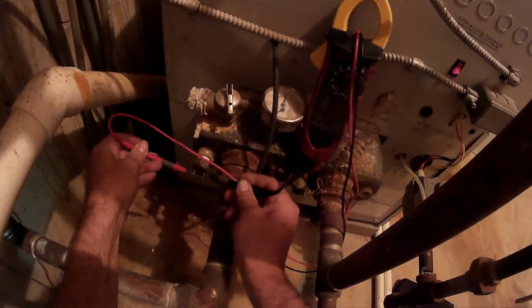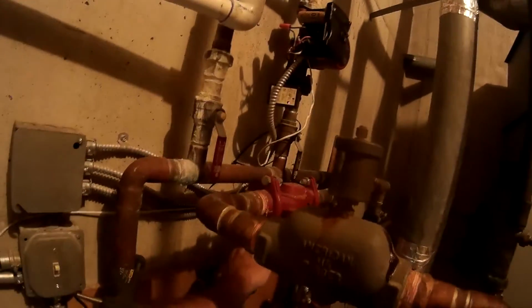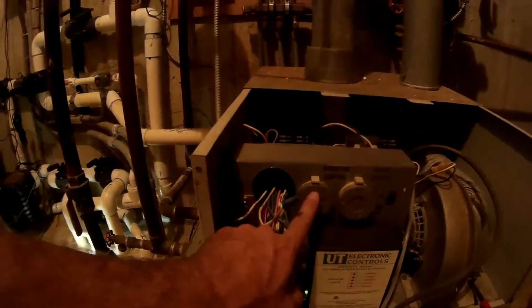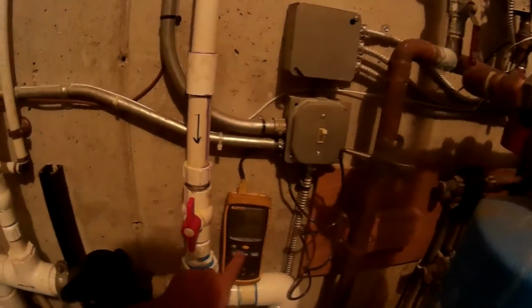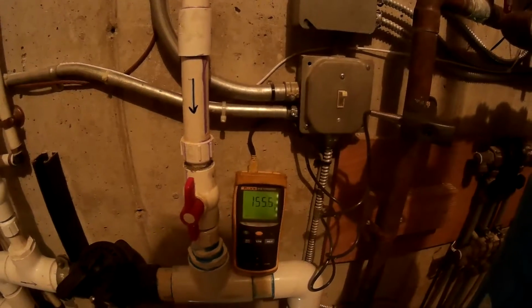So that high limit switch is bad. I have it jumped out for the time being just to do some troubleshooting. I'm not going to leave it jumped out for the customer at all, because I think what's happening is my pump is failing, because my pump was making noise. I got good amp draw on it, but the pump's making noise. And another thing I'm noticing is my operating switch, I'm set at 140 and I'm getting up to 160. Actually, with it set at 140, I'm getting it to 180. So my operator, which is that control, is bad. It's not keeping the correct temperature.